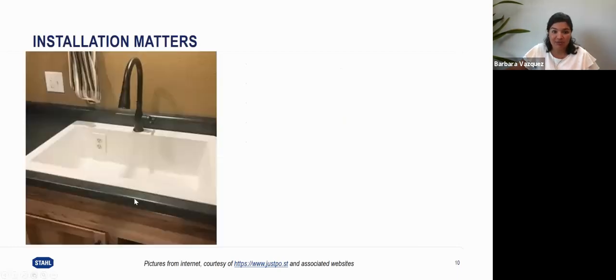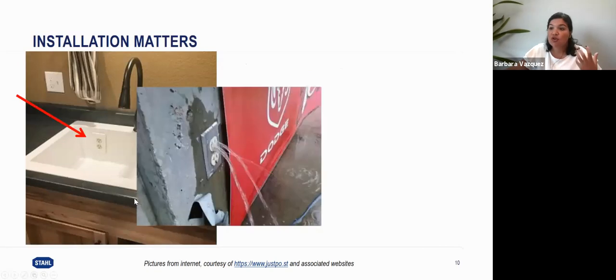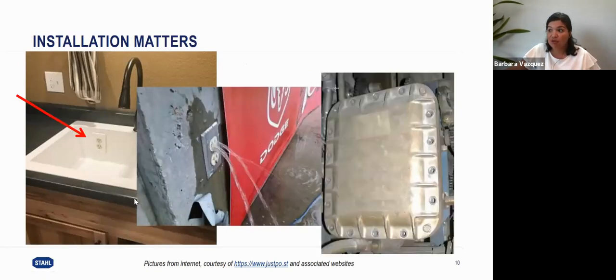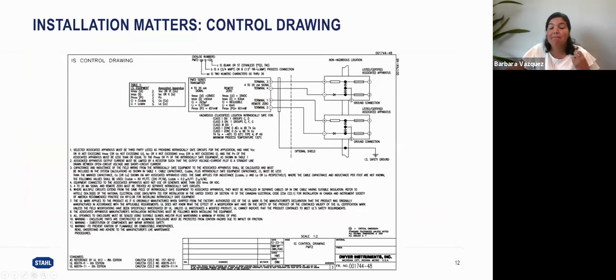Okay, but once we define and spec out the item for that specific hazardous area, we need to make sure we install it properly, right? Installation matters. So it is very important that we follow the rules for installation and do it properly. For intrinsic safety, one of the main documents you need to have handy, after the standard, of course, is the control drawing. For North America, every intrinsically safe device needs to have a control drawing. And we need to install it as per the control drawing. And this document is one of my favorites because it spells out very clearly what you can do with the instrument and what you need to follow.